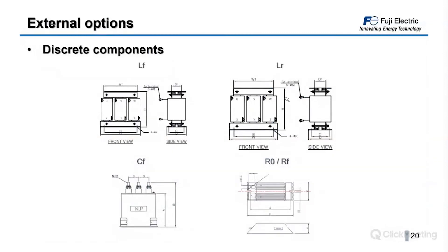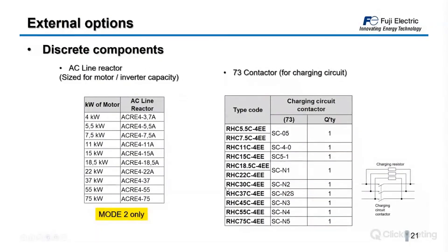The components look as expected: inductances look like inductances, and capacitors are mounted in a box. For Mode 2, a line reactor is used — sized according to motor or inverter power, using standard AC reactors from Fuji Electric. The charging circuit contactor references are provided by Fuji Electric, though standard contactors from any supplier can be used since they have no special characteristics.